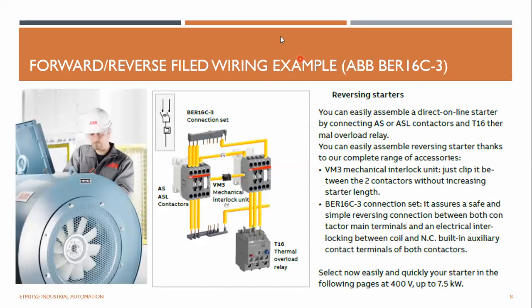And so this is a forward and reverse field wiring example from the ABB BER16C3 series. So this is how it comes. You can easily assemble a direct online starter by connecting AS contactors and a T16 thermal overload relay. This is a thermal overload relay. And you can easily assemble a reverse starter thanks to our complete range of accessories. VM3 mechanical interlock unit, just clip on between two contactors without increasing the starter line.